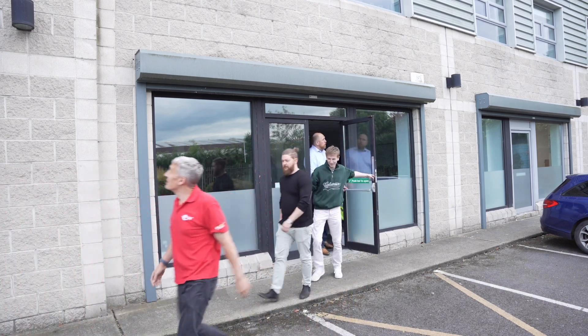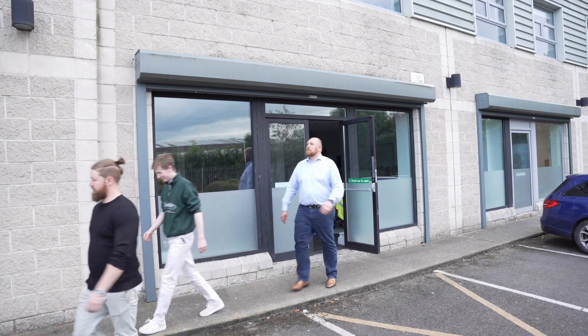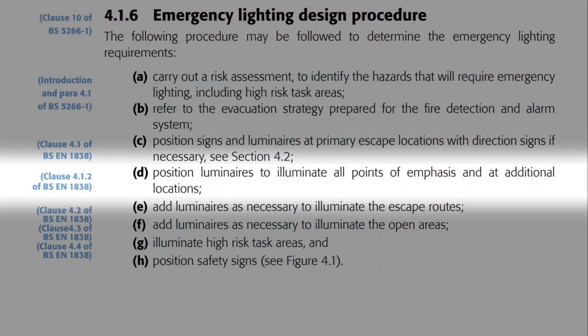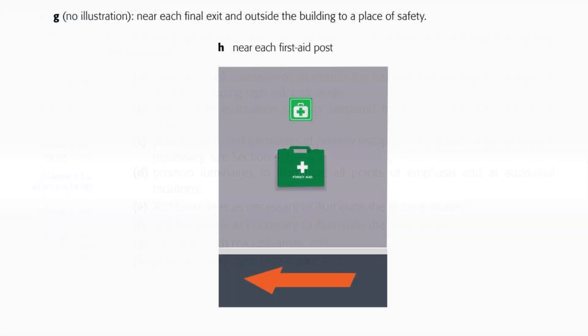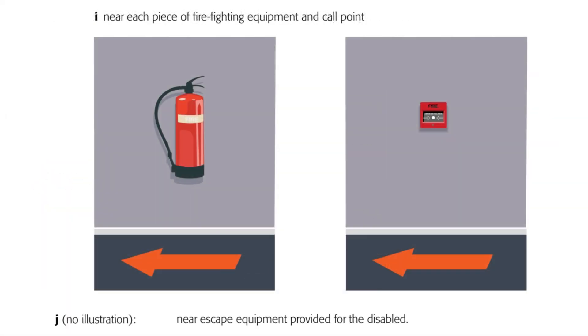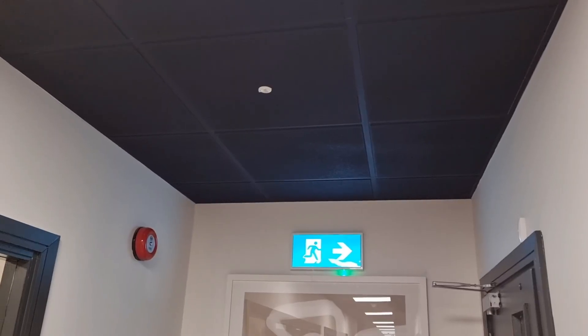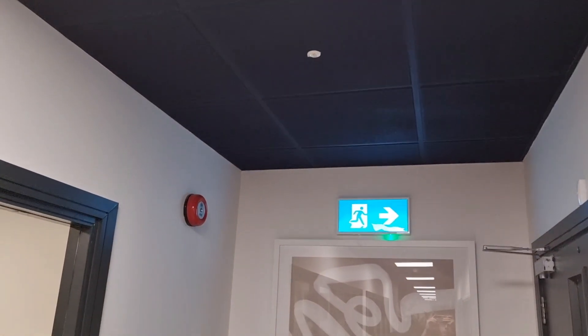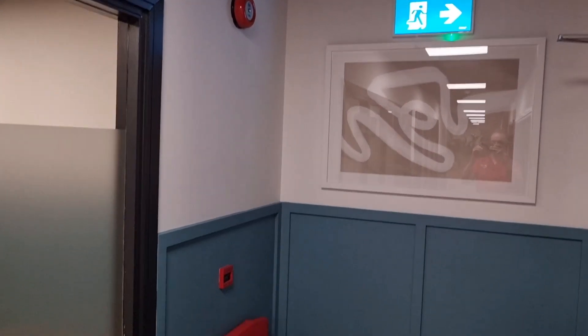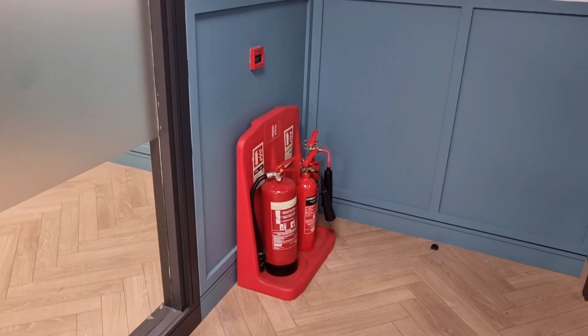Other items that require escape lighting luminaires nearby — which gets us into indent D of the design process — include first aid stations, firefighting equipment such as extinguishers and call points. The guide notes these items should have a vertical illuminance of at least five lux. When carrying out lighting design we often get focused on horizontal illuminance near the floor or work surface, but we must not forget about light levels in the vertical plane on walls, monitors, signs and emergency equipment.